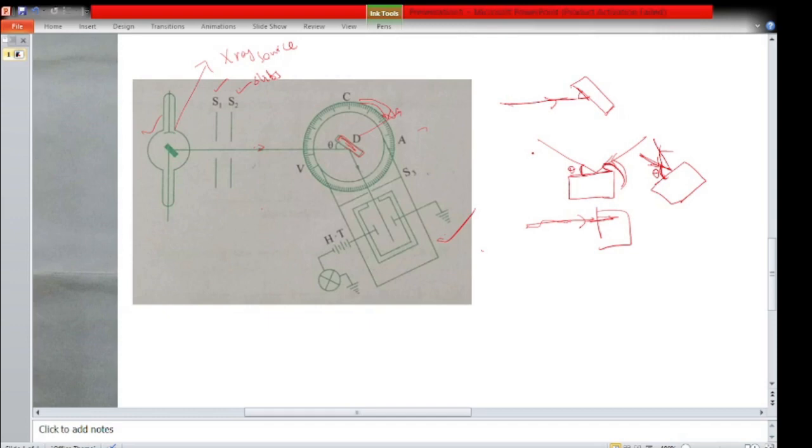You can use a photographic film, or you can also use an ionization chamber. Why ionization chamber? If the X-rays are passing through that ionization chamber like this, that will produce some ions and electrons. You know how this ionization chamber works. When the radiation comes, it will produce some ions inside this ionization chamber, and that will produce some current. Depending on how much current is produced, we can measure how much radiation is there. So we can say this much intensity will be there. We can distinguish the bright and dark spots.